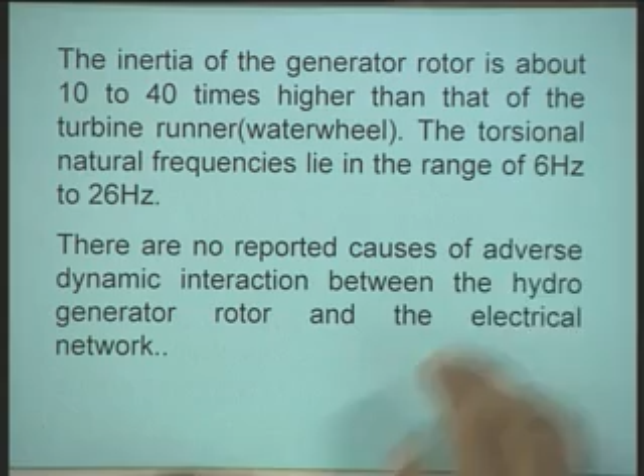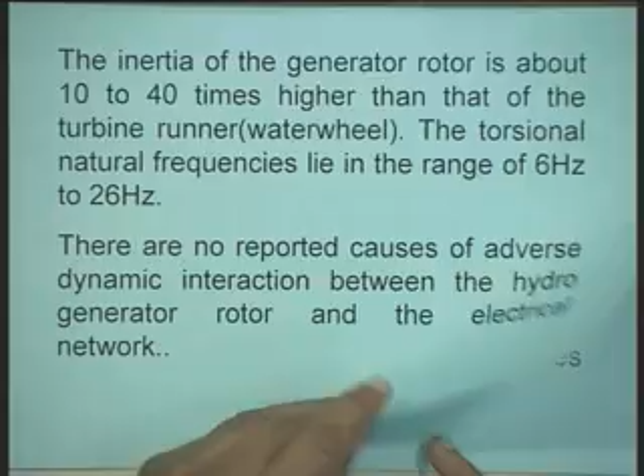The inertia of the generator rotor is about 10 to 40 times higher than that of the turbine runner or water wheel. The torsional natural frequencies lie in the range of 6 to 26 hertz. That is because of the vast difference in the inertia constants; the torsional frequencies are in this range of 6 to 26 hertz, which is a typical range. There are no reported causes of adverse dynamic interaction between the hydro generator rotor and the electrical network.